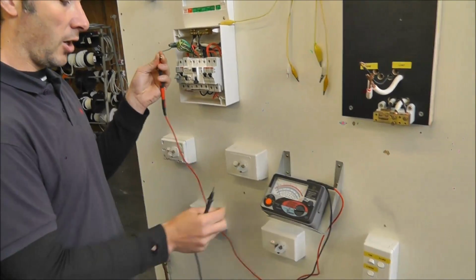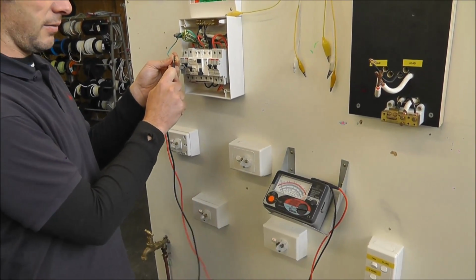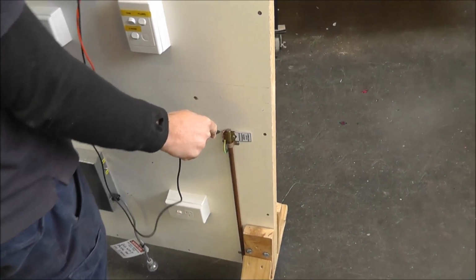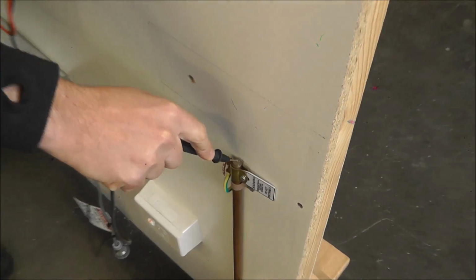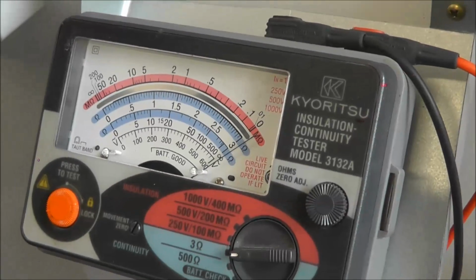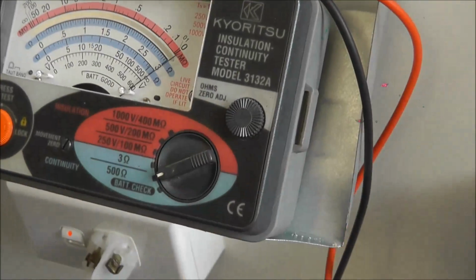Okay, from the disconnected end of the main earth, let's see that we're good here. I'm on 0. Over to where? Do I go to the conductor or to the stake? To the stake. Now look here, Dobbo, have we seen anything move there? No, I have not. So what should I do there? Is that infinite? Move on? Next scale. Next scale, Matt, well done.